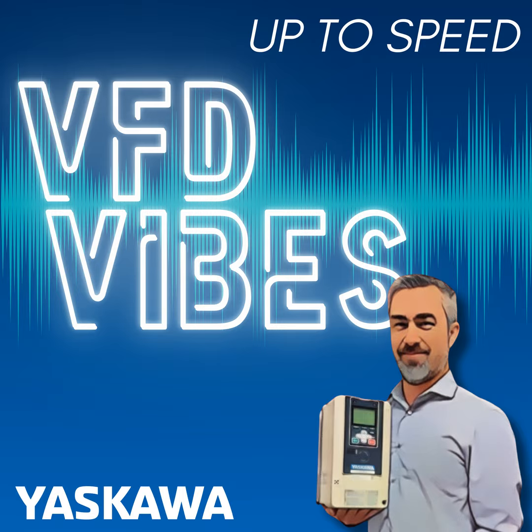Now, Yaskawa has a patented feature that we use in the IQ Pump and many of our other drives that will actually detect this imbalance. The biggest problem with these open delta systems is imbalance. The drive wants to see a balanced 3-phase system. If the 3-phase system is not balanced, we start to put stress on the bus capacitors. The typical ripple on the DC bus of a drive from a balanced 3-phase system occurs at 360 hertz, in other words, 6 times the 60 hertz of the power line.